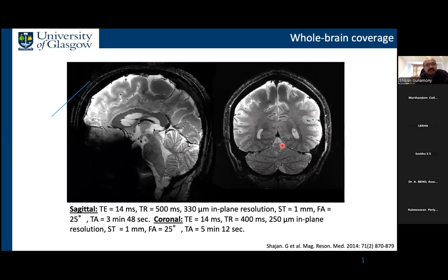Yeah, so we can categorize these kind of ultra high field coils in two groups. The first one is transceiver coils, where we use the same coil to transmit and receive. And then there are transmit only, receive only coils, which is the one I showed just now, where we have a separate transmit and a separate receive coil. So with transceiver coils, you can bring the coil close to the head, so then you produce a much stronger B1 field. Whereas in this kind of coil, you want to have space for the receive coil, so the transmit coil will be large.